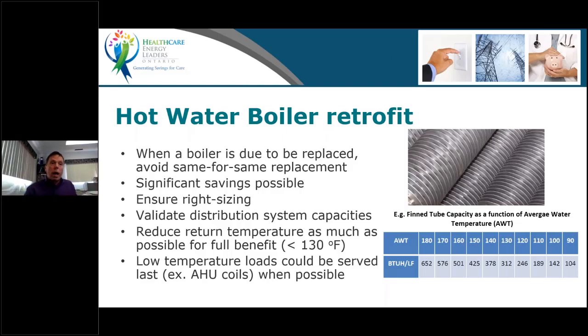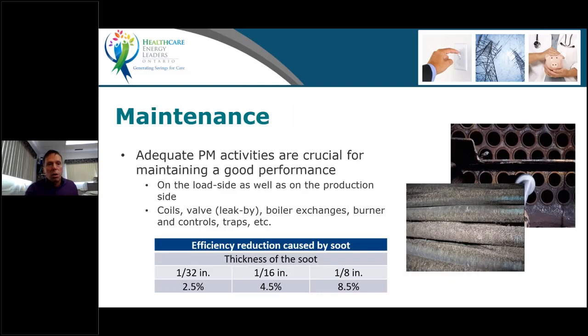If you have a condensing boiler and you have low temperature loads, you try to serve those at the end. So a makeup air unit, for example, if it can be on the return, you send the water to the makeup air unit coil last. That one will drop your temperature because that's a low temperature load. It's outside air, it's cold. It can actually drop that return to a lower temperature to improve condensation for a condensing boiler. Like I said, you have to think all those things through when you do boiler replacement. Now we're going to talk about maintenance.